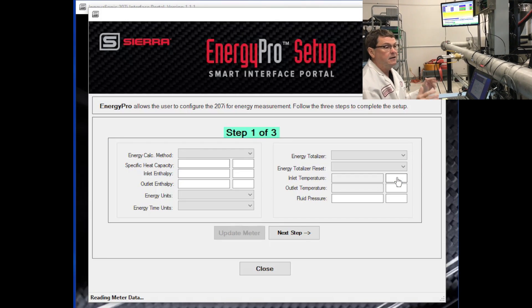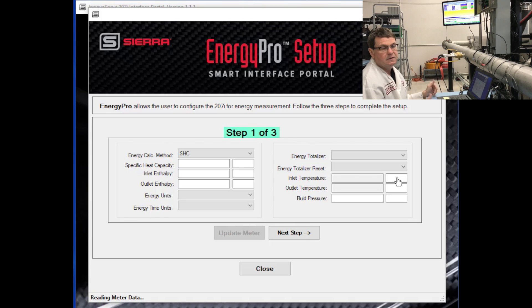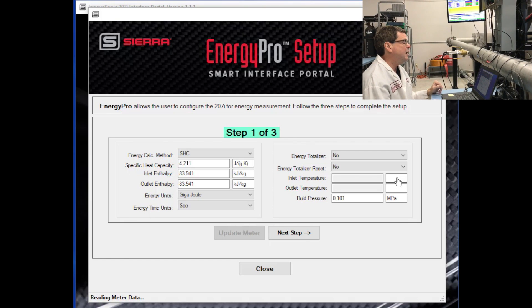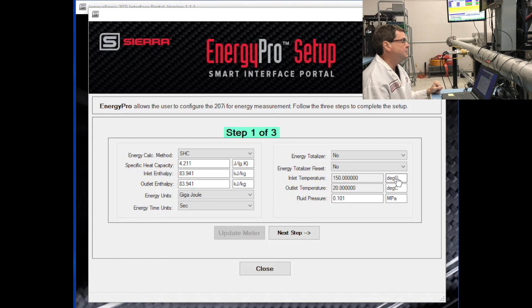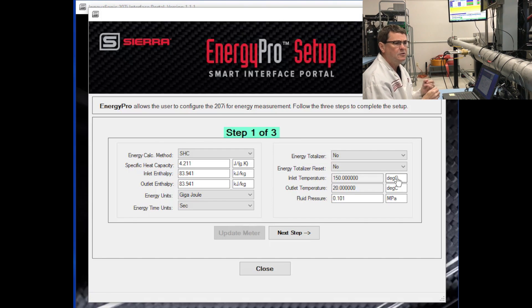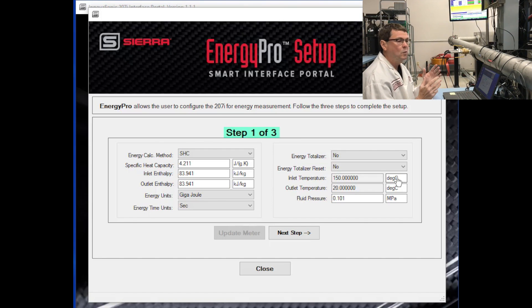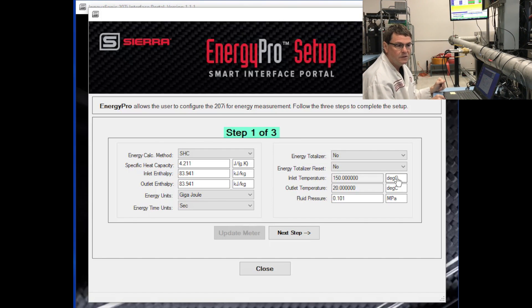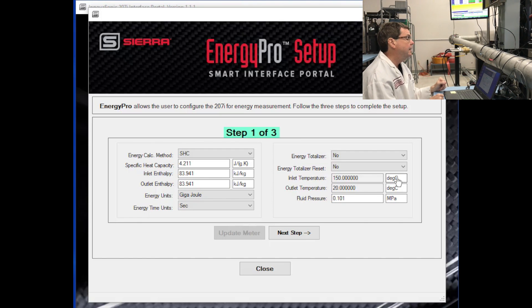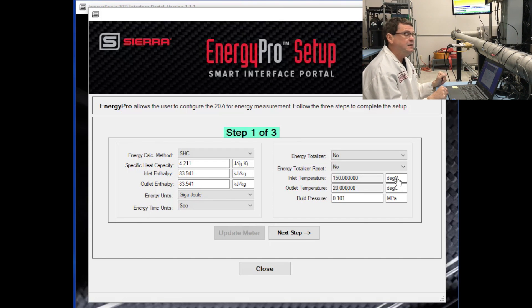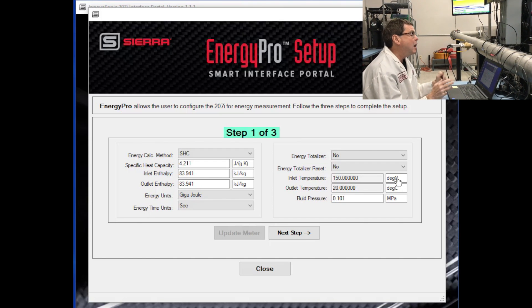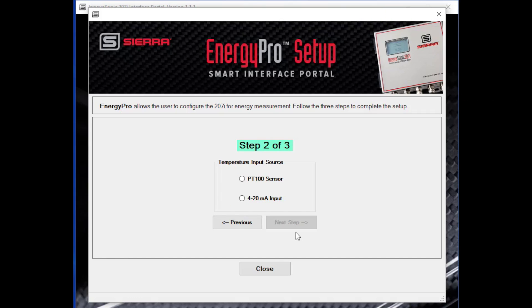And again, it's divided into steps. In this case, three steps. Step one is to set up the basic energy measurement. What units do you want to use? How do you want to calculate energy? There are various methods to do that. Put the basics in for step one on how you want to actually make the measurement. Step two is to identify what the temperature input source is. You can have a PT100 sensor. We have insertion versions of those. We have a clamp-on version that you can use. Or you can use your own, purchase your own.